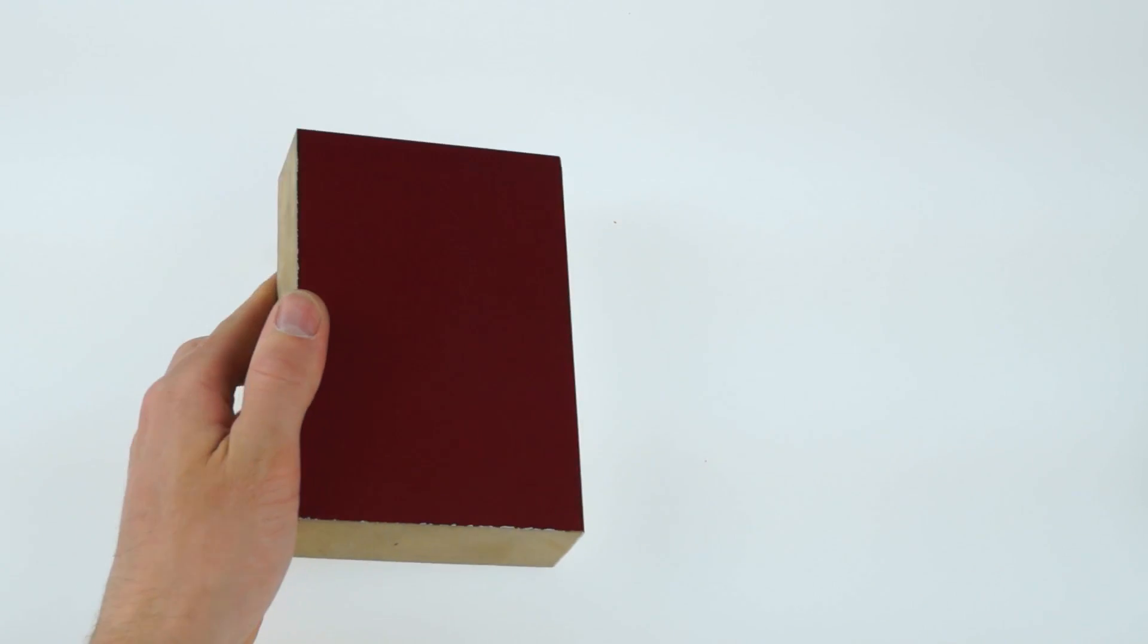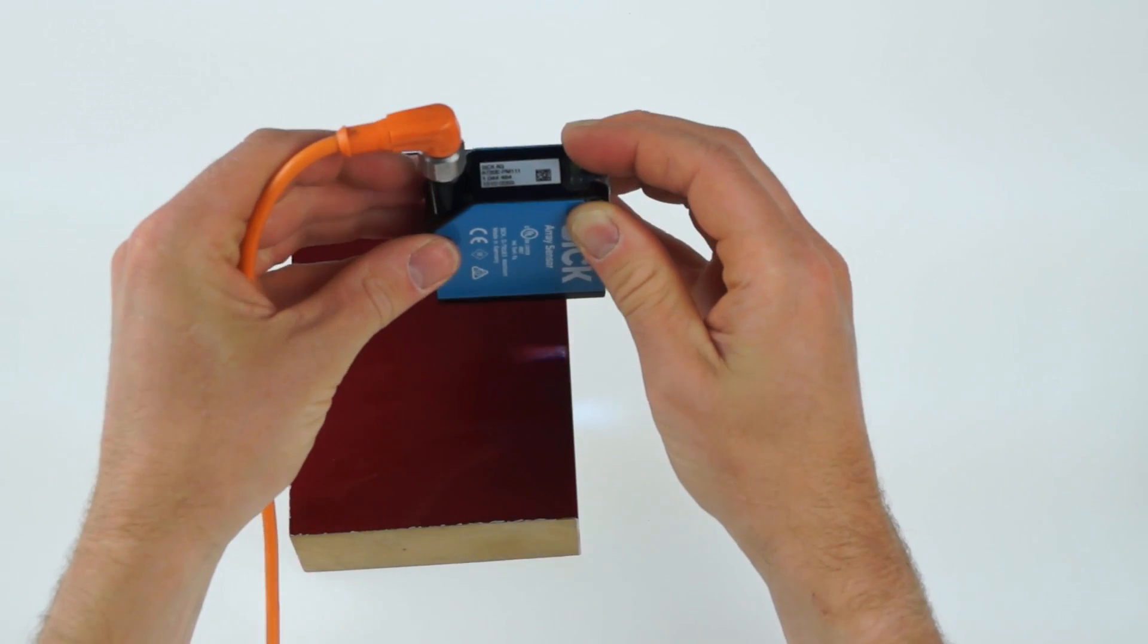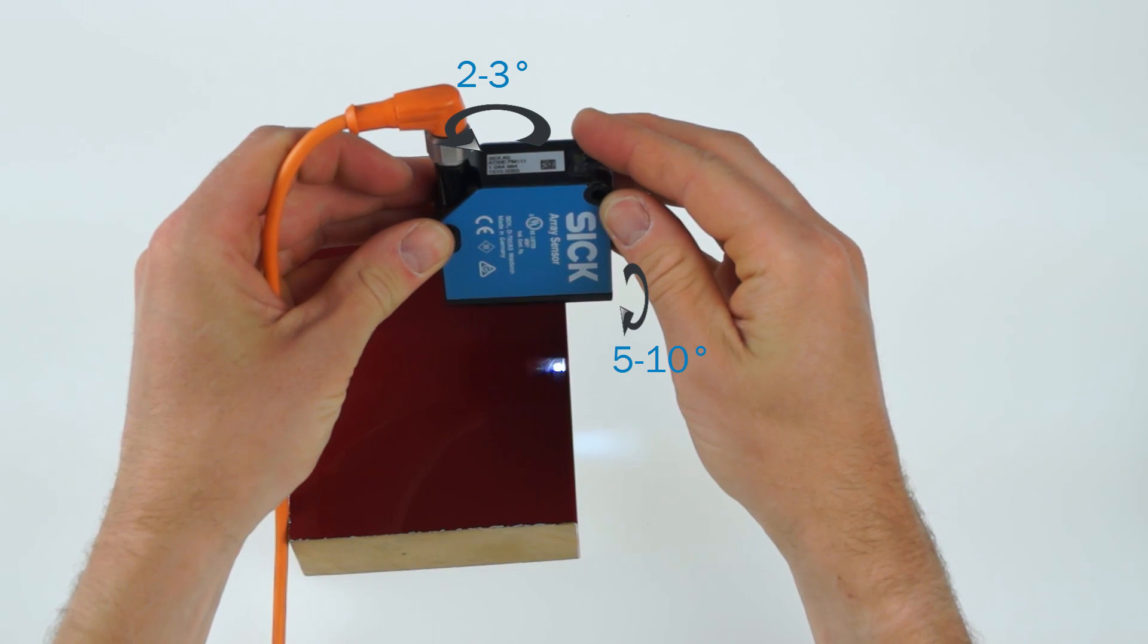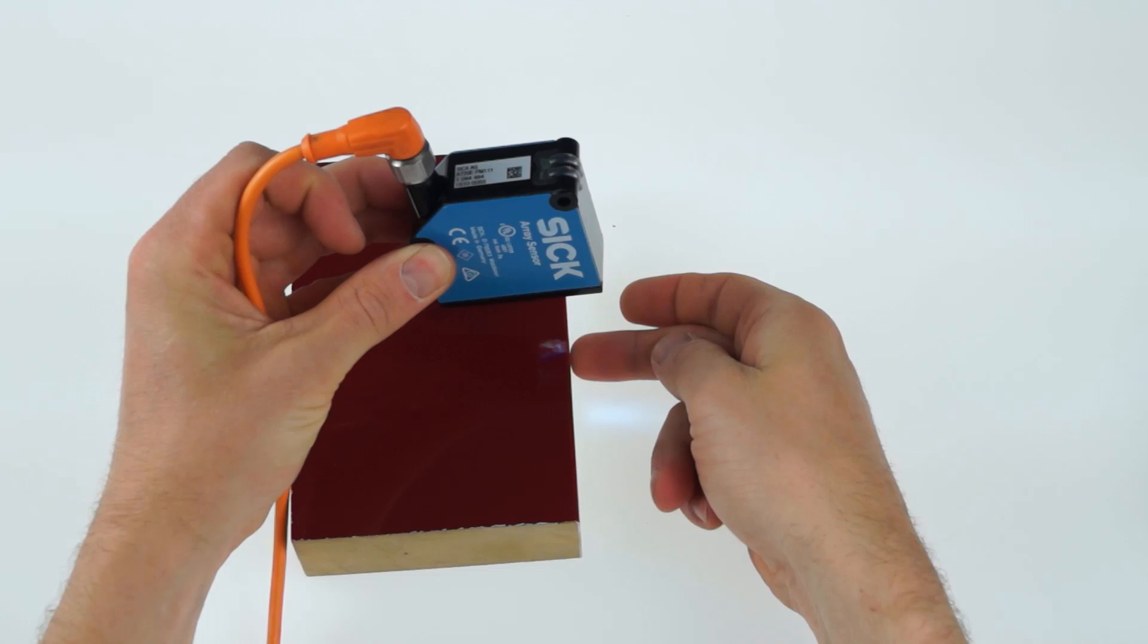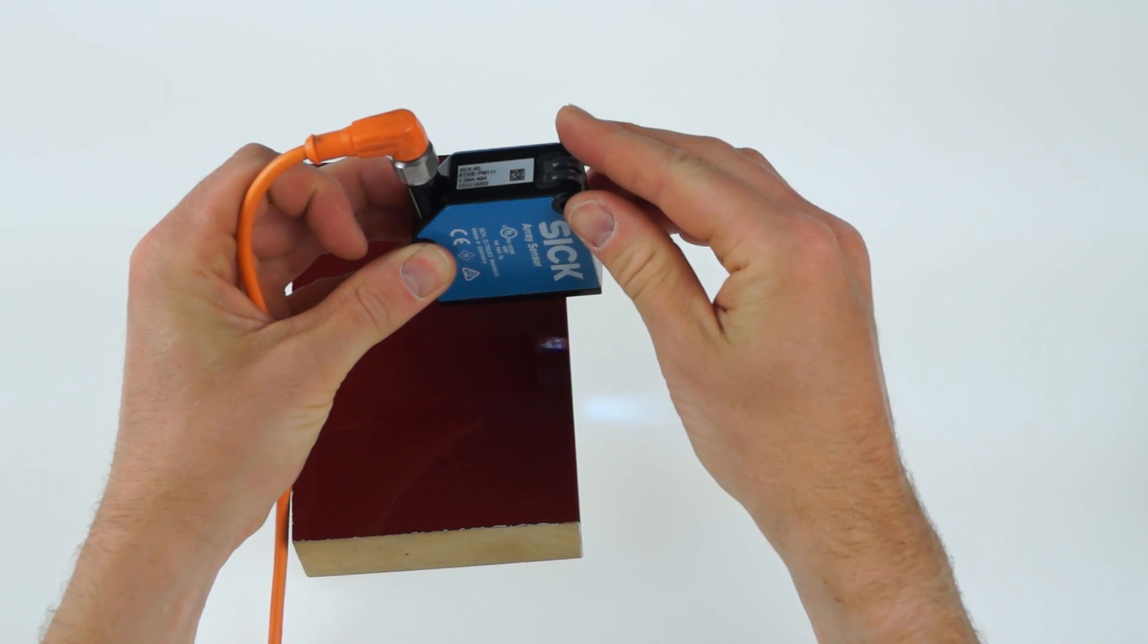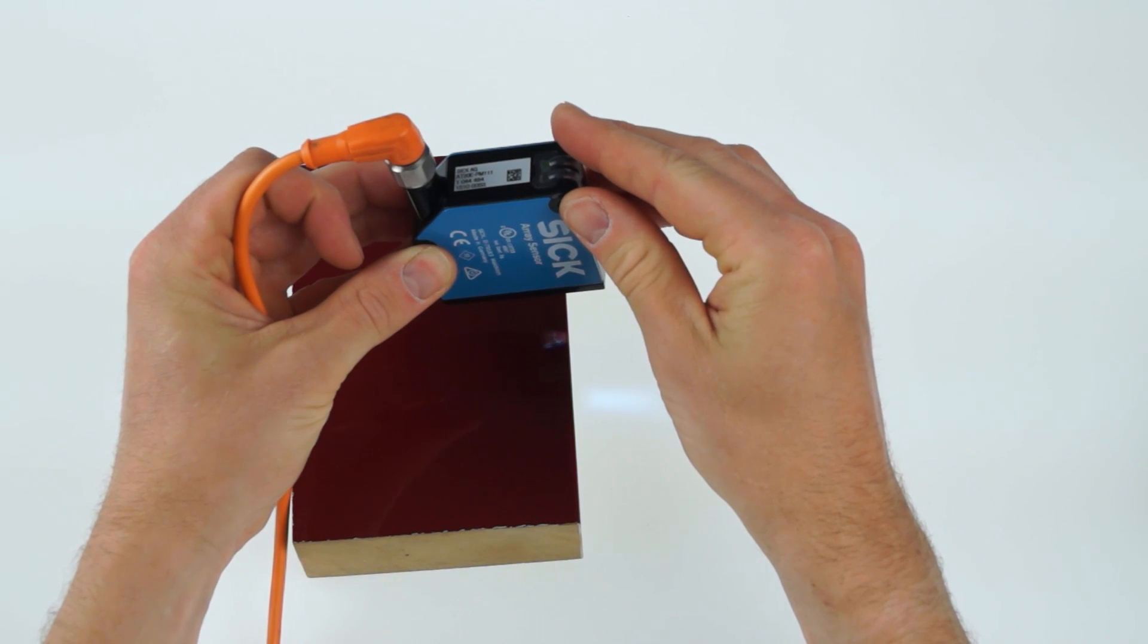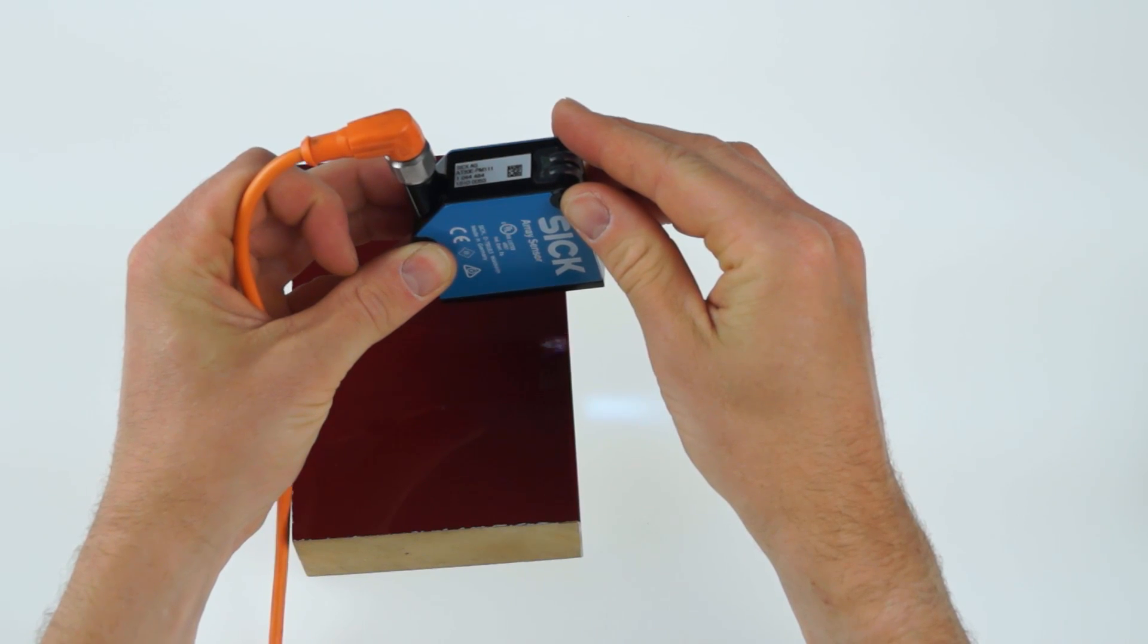If thicker material like this coated wooden board needs to be detected, it is recommended to work with an approach angle of 2 to 3 degrees in order to avoid double switching at the edges which come from reflections at the lower edge. The angle needs to be in a way that the lower part of the object is shadowed.